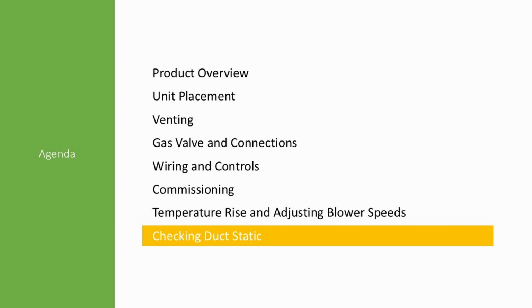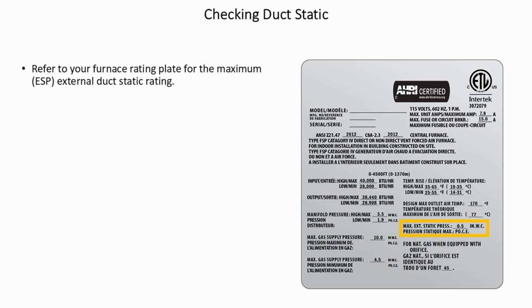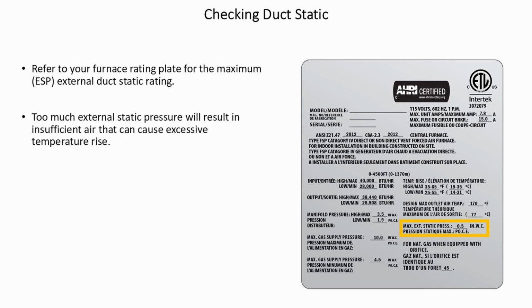Checking duct static. Refer to your furnace rating plate for the maximum ESP, external duct static rating. Too much external static pressure will result in insufficient airflow and can cause excessive temperature rise. This can cause limit switch tripping and heat exchanger failure.